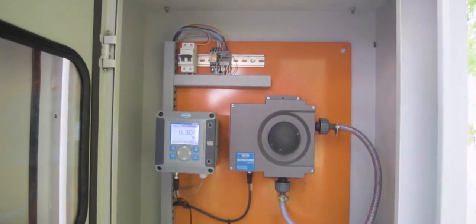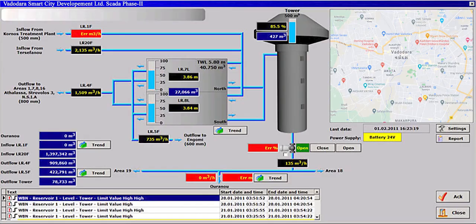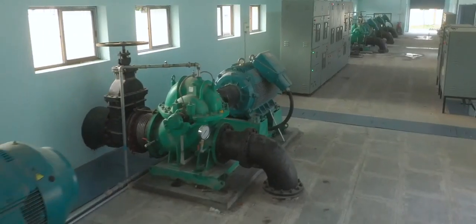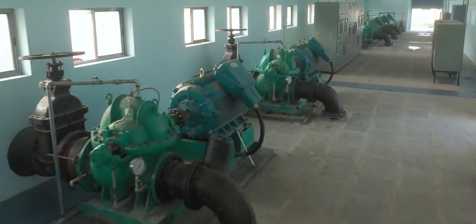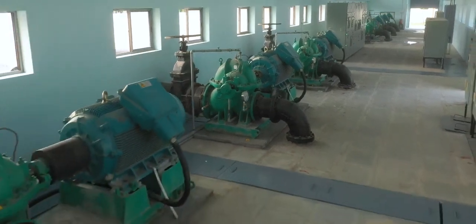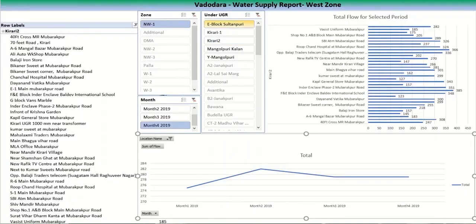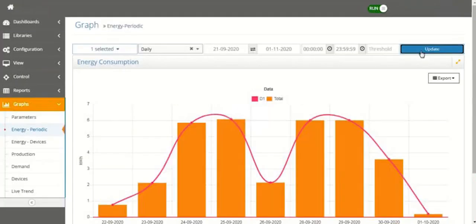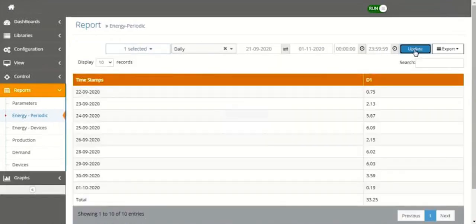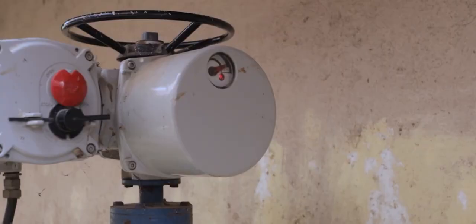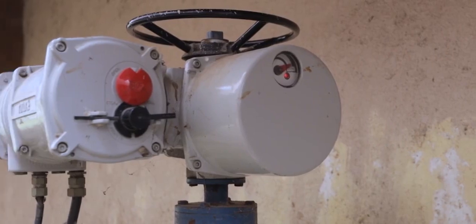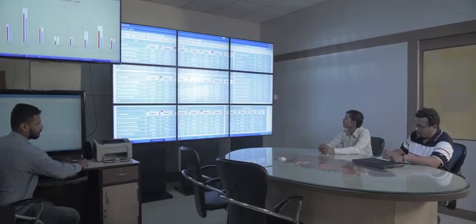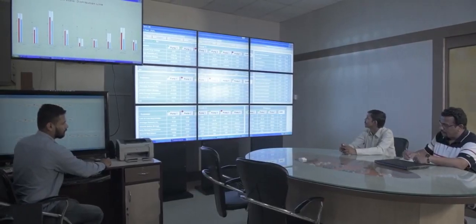Monitor the quality of water being supplied to the residents of the city. Calculate efficiency and health of pumps along with a real-time and historical audit of energy consumption on account of pumping. The automated valves can also be remotely operated over GPRS communication from the SCADA center.